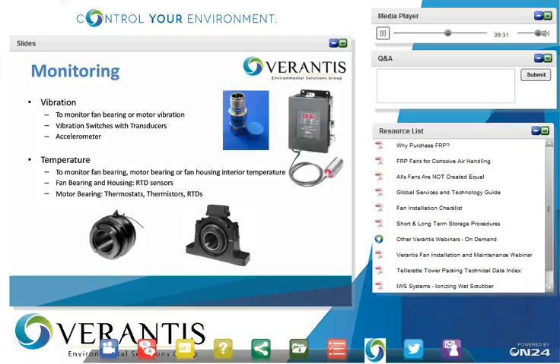Bearing temperature and motor temperature are a very important indication. When the temperature goes high, it could be because of a high vibration level, and it could also be because of lack of lubrication. Also, because of FRP fan material, we recommend you install a temperature sensor at the interior of the fan housing, just in case something happens throughout the process system and causes a high temperature that causes failure of the fan. Usually for fan bearing or the housing, we can use RTD sensors and send all the signals to the control system. And for motor bearings, we can use thermostats, thermistors, or RTD sensors.